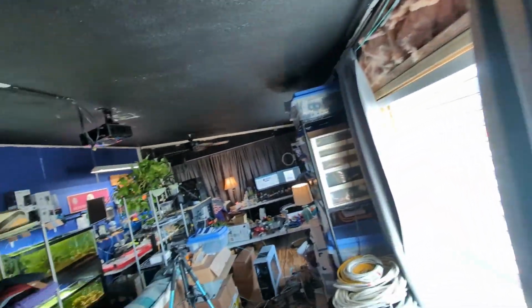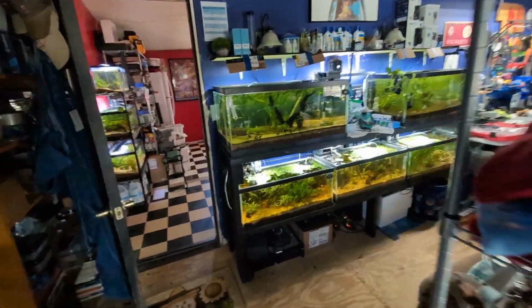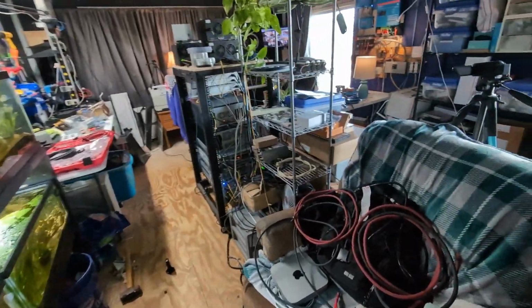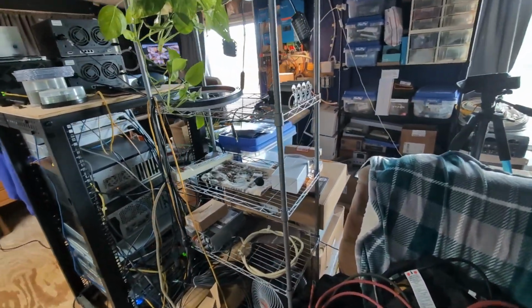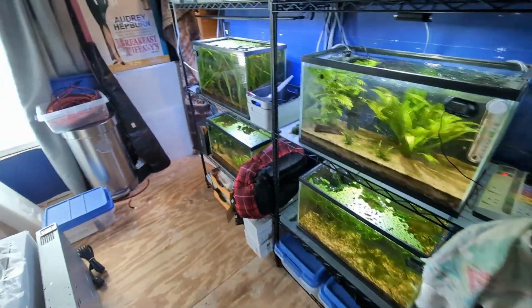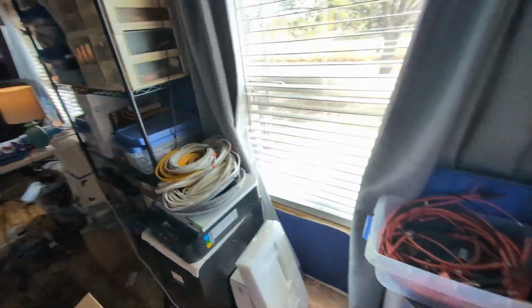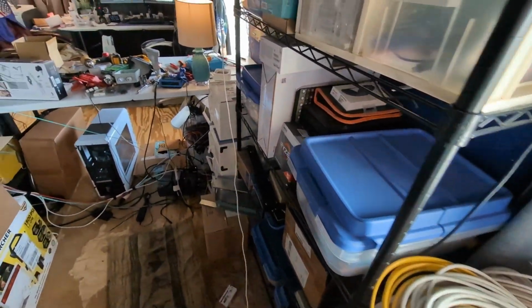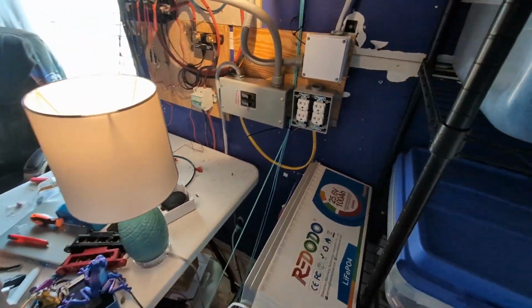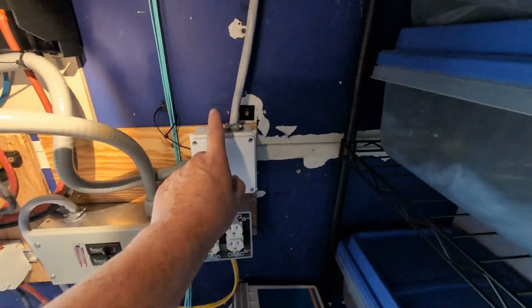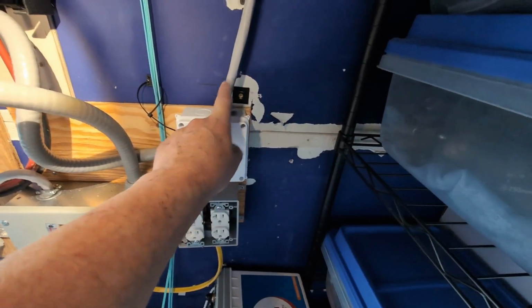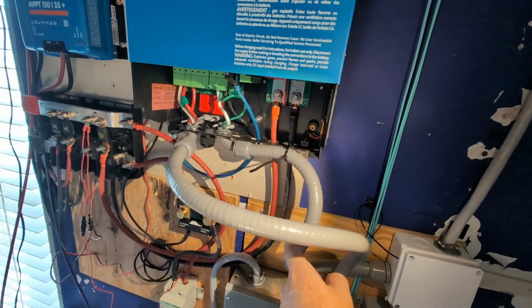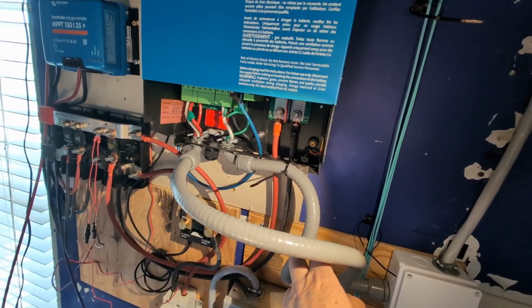Flip that on. That sends power up over that wire, a service entrance cable, that's why it's not in conduit. It comes over to this gray box. Hang on, I'm trying to get the best view here, I'm out of breath, I'm an old man. So it comes over to here, and that power gets converted from aluminum to copper cable because the Victron does not support aluminum wire.